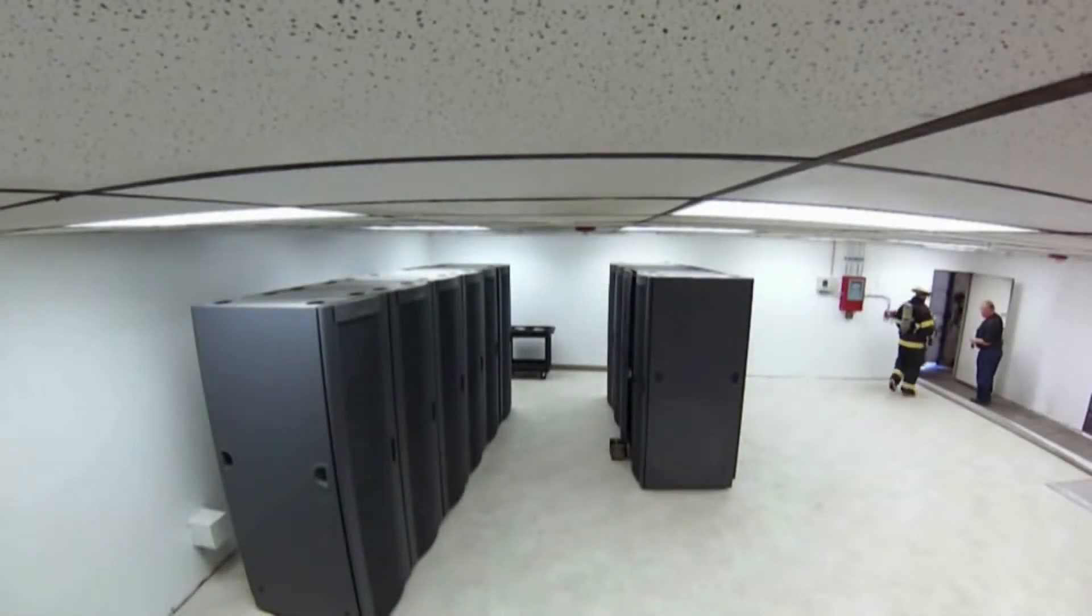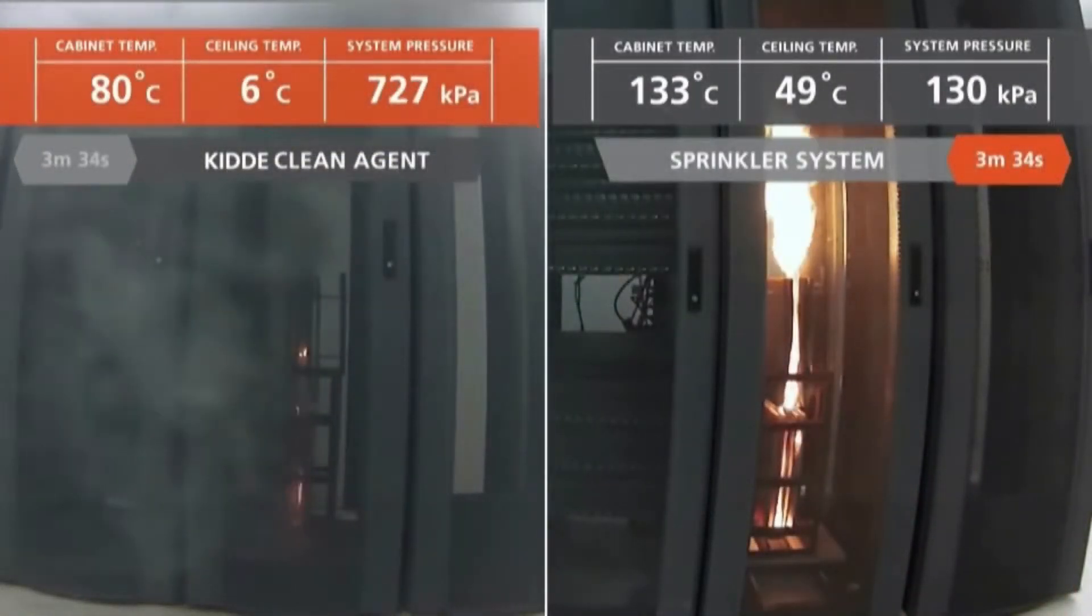The water sprinkler test begins the same way, but nearly four minutes elapsed before the first sprinkler head discharges.